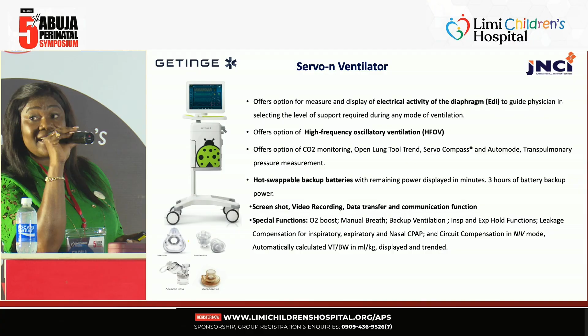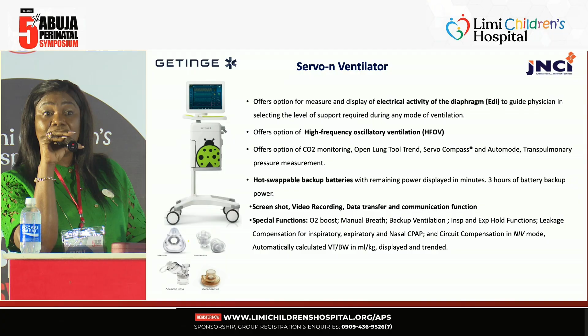But in this ventilator, we have a tool called the lung monitoring tool, or open lung tool, that helps to assess this. It makes it easy for you to tell if your pressures are too high, irrespective of the baby's weight, because a lot of our therapies for neonates are weight based. However, for some of them, we do not know the status of their alveoli. So the open lung tool helps you to actually see, even when you use the lowest of tidal volumes, 4 to 6 mils per kg, whether you're overshooting your pressures or your volumes. This helps you in identifying that. Another key factor is that it has hot swappable batteries.